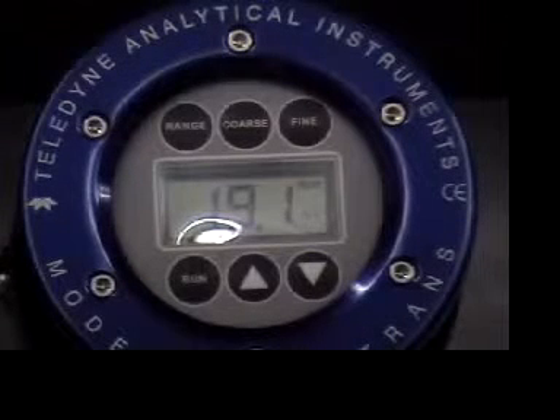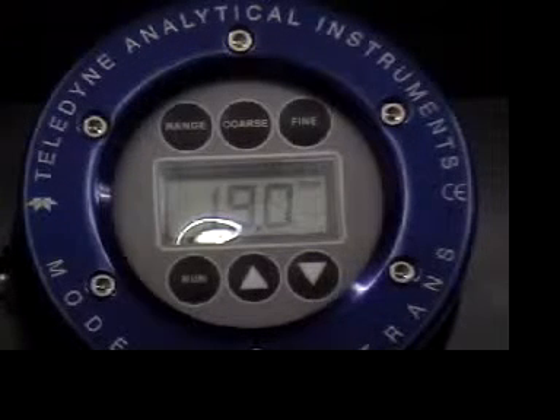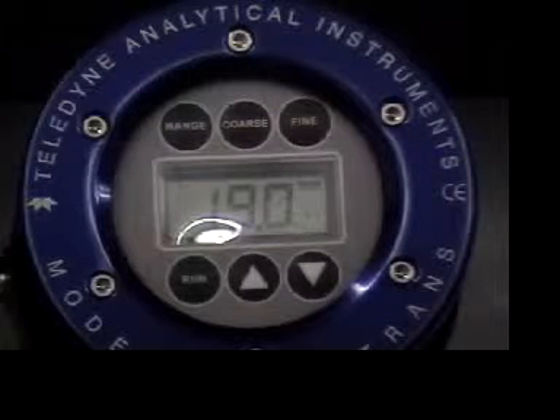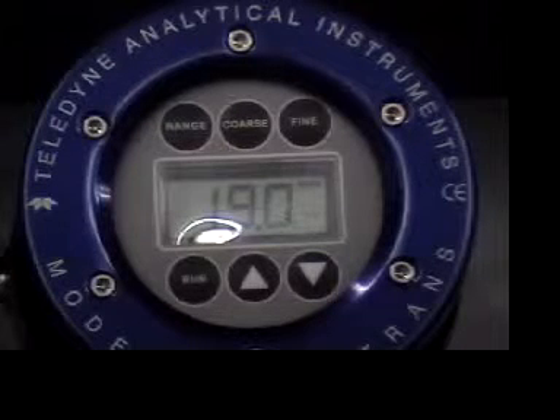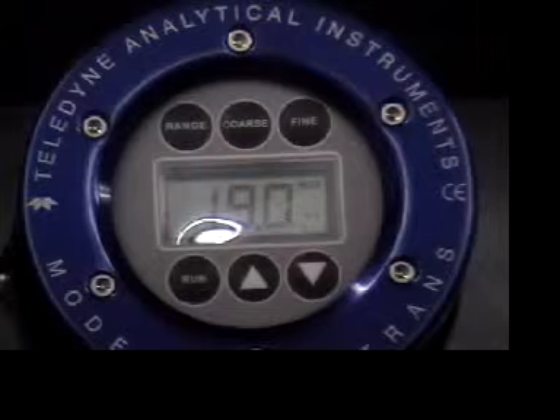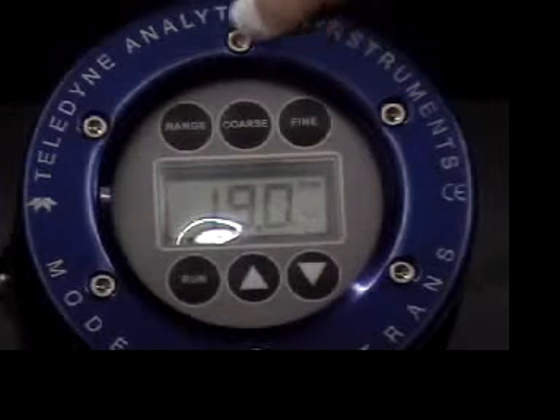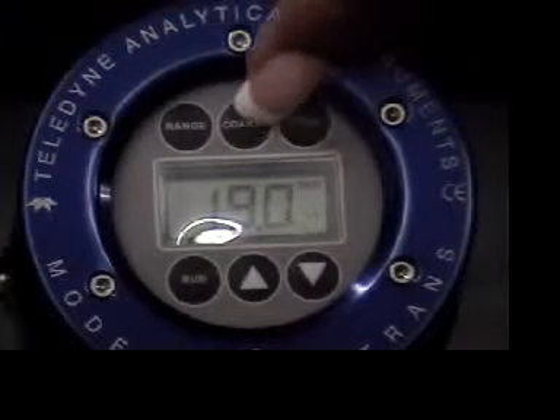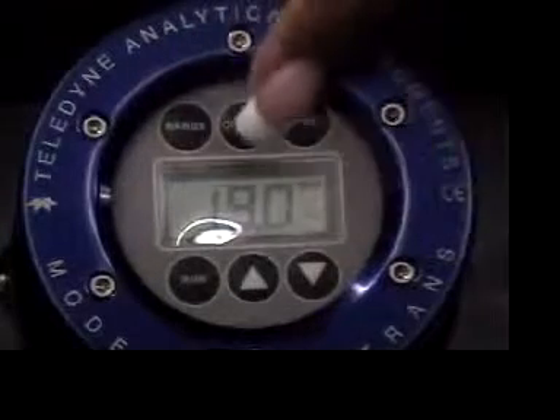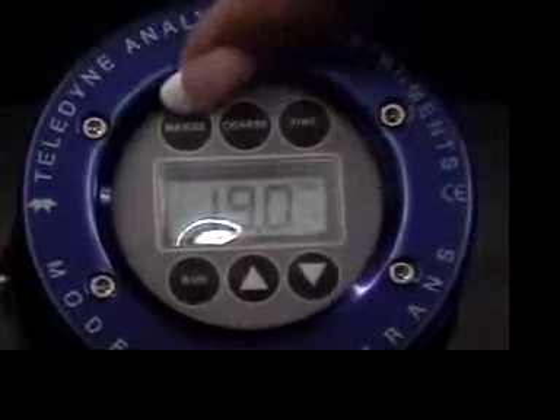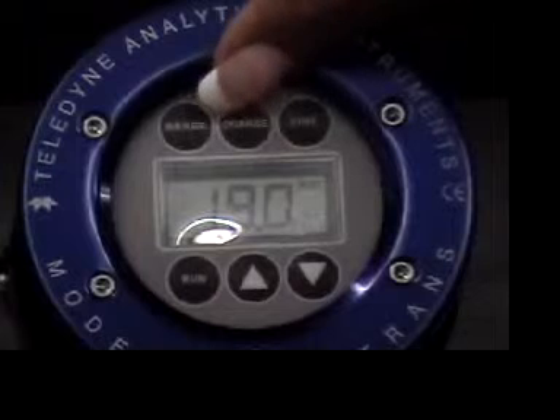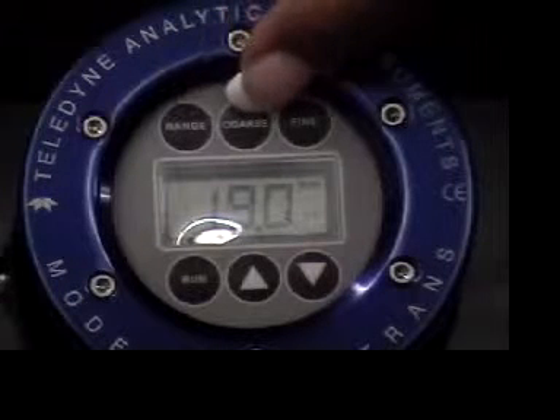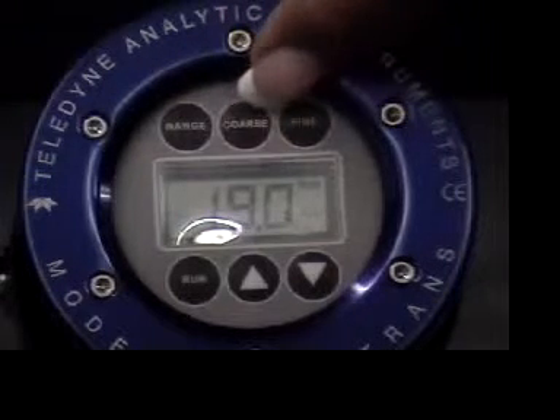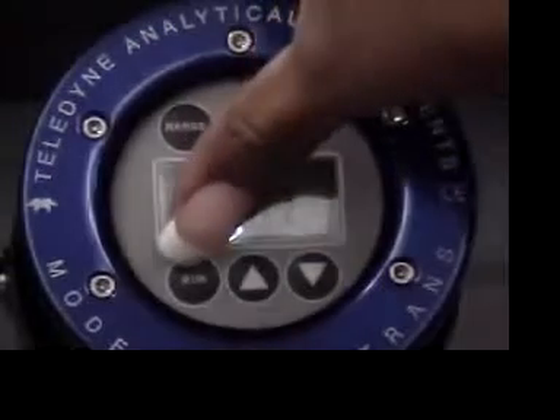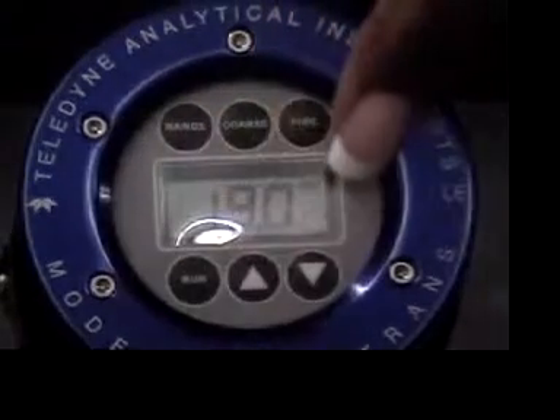Now that we have the oxygen sensor installed, I can go ahead and demonstrate how to do the calibration on the oxygen transmitter. You have 3 buttons on top and 3 on the bottom, and your display in the middle. Actually, there's the range switch, the coarse and fine adjust selection, the run mode, and the up and down arrow.